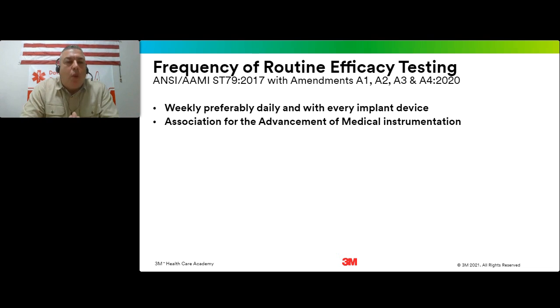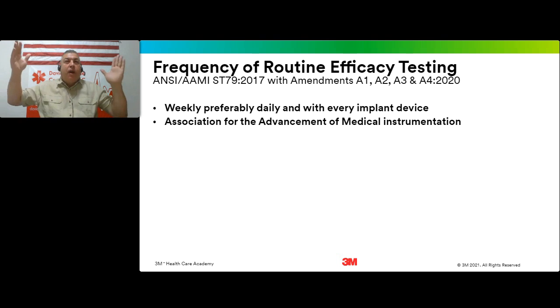We talked about weekly, preferably daily, for the BI testing. This is directly out of the AAMI document. We talk about that because if you're a facility just running a test on Monday, some people batch their implant devices if they can, and tend to try to run them all on one cycle. So potentially, based on the nature of cases and procedures done, if you test on Monday, there could be a potential that you go a day or days before an implant device is put on a cycle and another BI test is run.